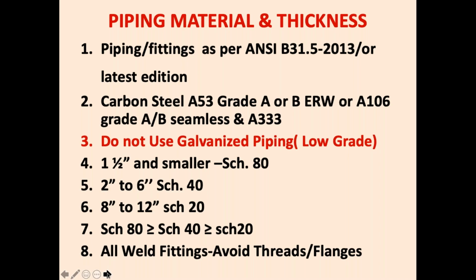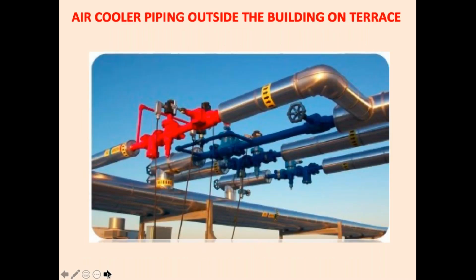All weld fittings, I have already told you, avoid threads or flange joints to avoid leakages. I have told you that sometimes it is not possible to reach the controls in air coolers, in cold storages, especially in minus 20 degrees rooms, because operators will hesitate to operate any control at that temperature, and welding and other things are not possible. So my suggestion, except the air cooler, as we discussed last time, keep everything outside. All controls should be available outside the air cooler wall, and they should be easily operable for maintenance and for adjustments. So this is the good practice.